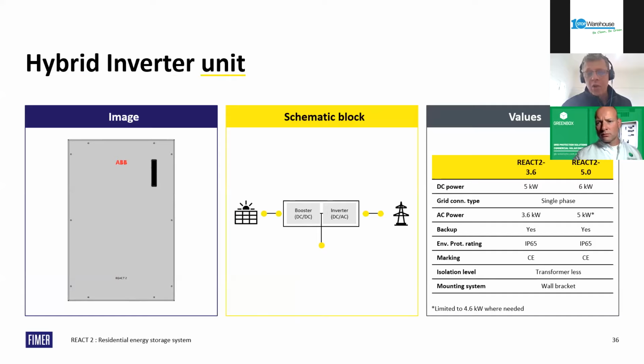Before I go into the battery side, you can install a React 2 inverter, and during the day, when there's capacity on the array and in the event of a grid loss, it does give you backup without batteries. So there is a 3 kilowatt backup circuit on the React 2 inverter module. So if you lose the grid during the day and there's capacity on the array without batteries, you'll get an emergency backup supply.